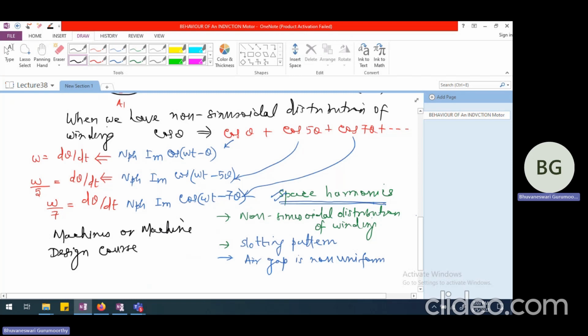The space harmonics are responsible for crawling. You might have heard of this phenomenon called crawling, where the machine gets into a speed of omega divided by 5 or omega divided by 7, where omega is the synchronous speed. So if the synchronous speed is 1500 RPM, the machine might rotate somewhere close to 300 RPM, which is omega divided by 5. That phenomenon is generally known as crawling, and it is the result of space harmonics.